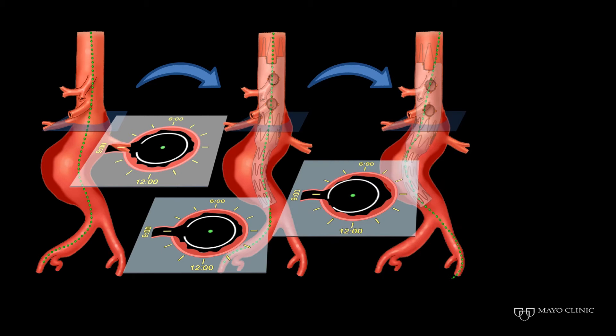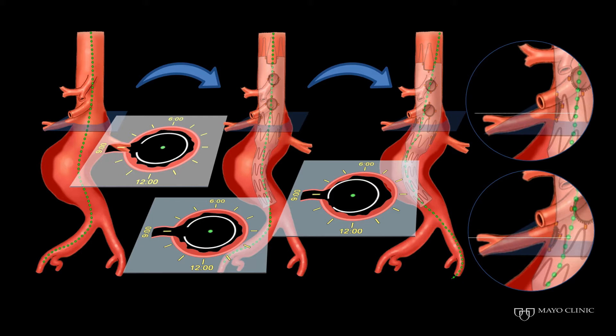This is an example of how we design these stents based on a center line of flow so that the fenestration matches exactly the orifice of the branch vessel. That works well theoretically. However, as we move the device and take into account the tortuosity caused between the axis of the iliac arteries and the visceral segment, the fenestration is often displaced laterally against the wall of the aorta or anteriorly. This is even worse when the operator places the stent graft slightly higher or slightly lower, as demonstrated on this slide.